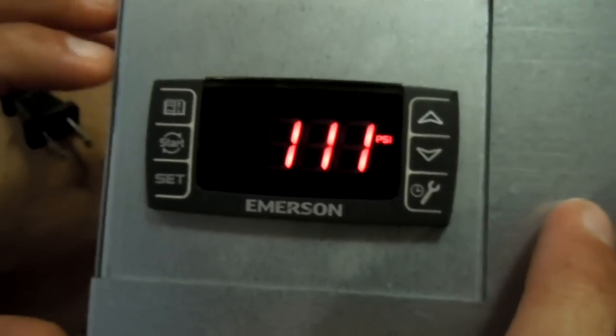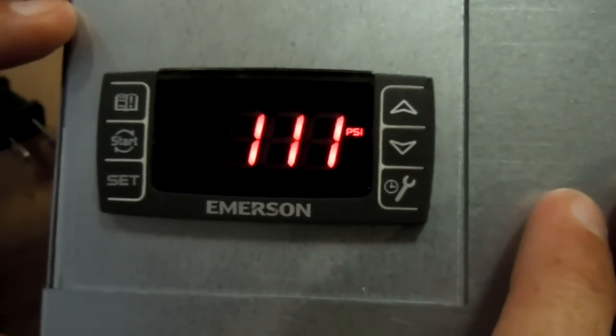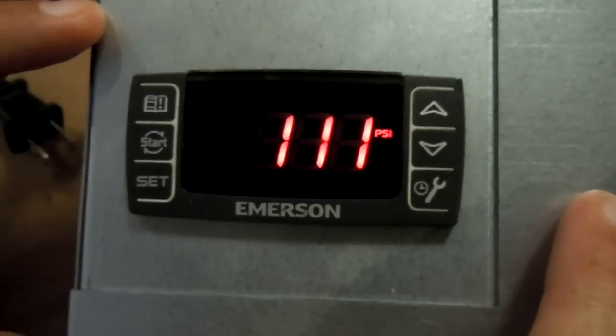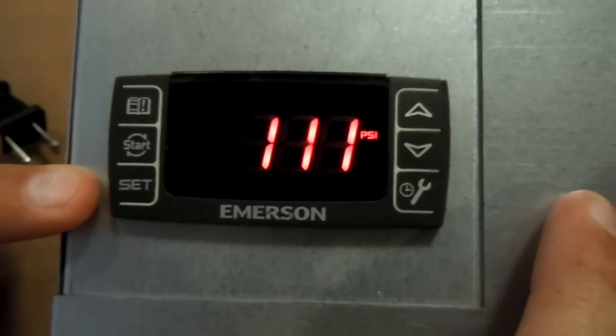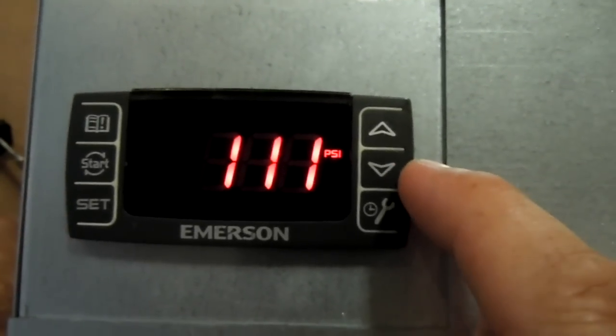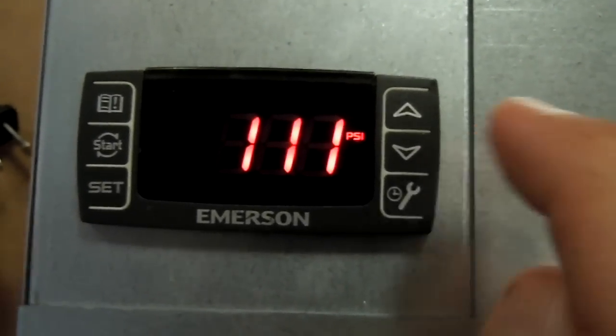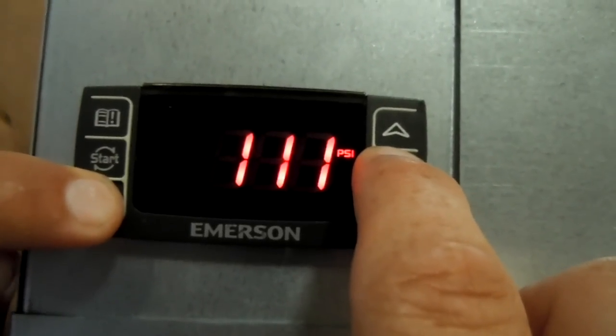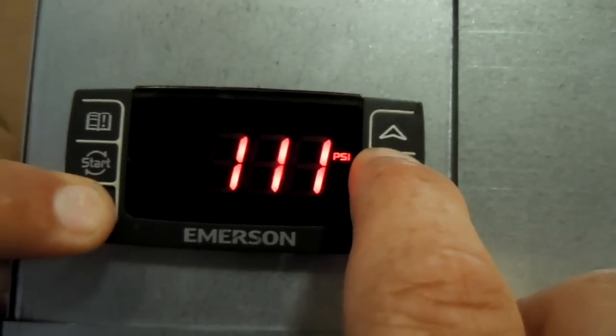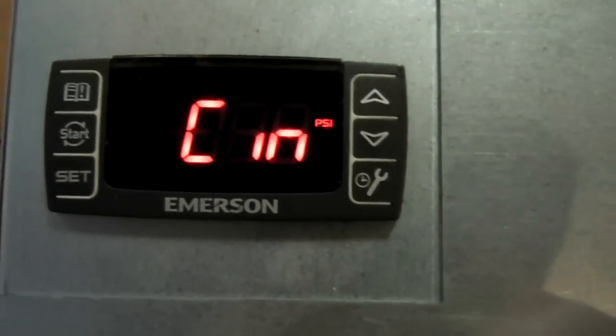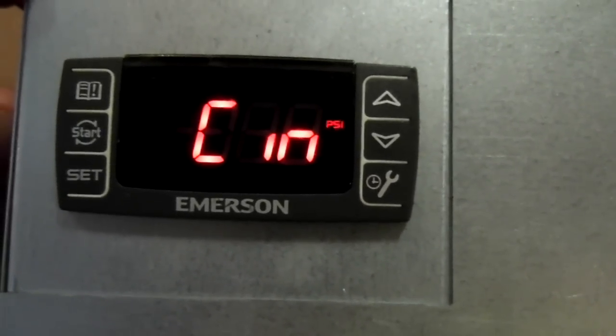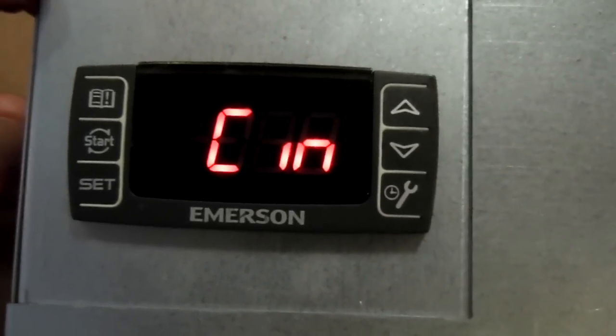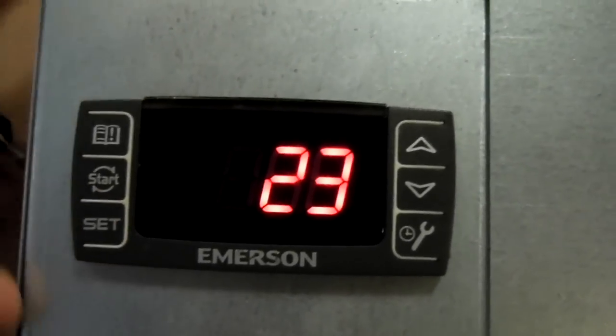Okay, first of all, to get into the quick setup, to set up your low pressure parameters, you hit the set button and then the down arrow for five seconds. And then that is going to put you into the cut in mode and hit set again.